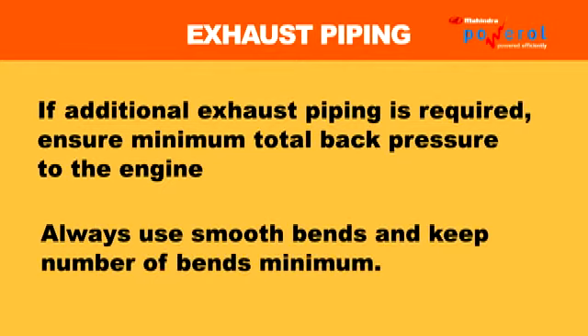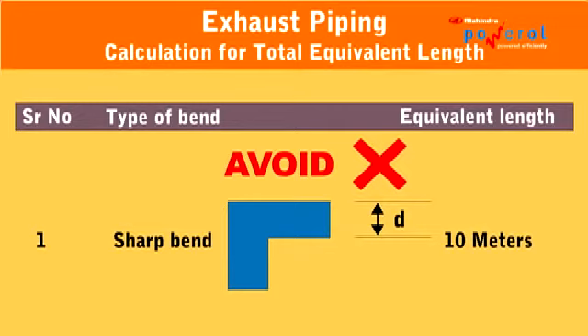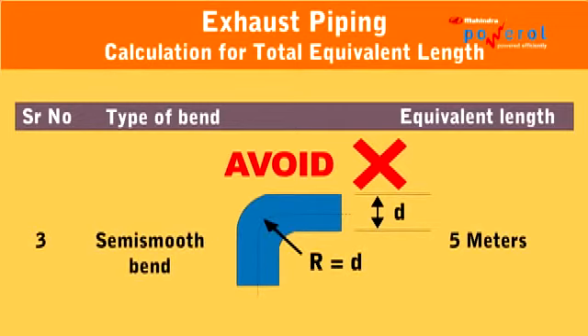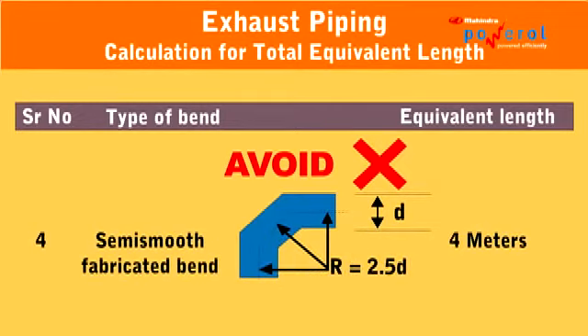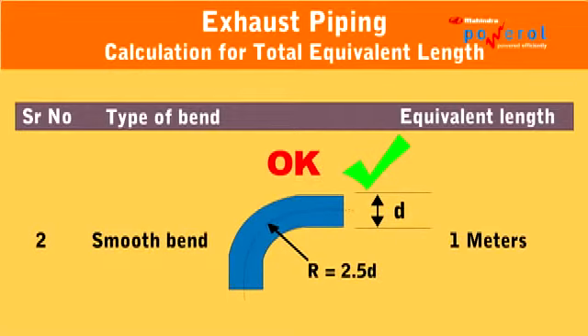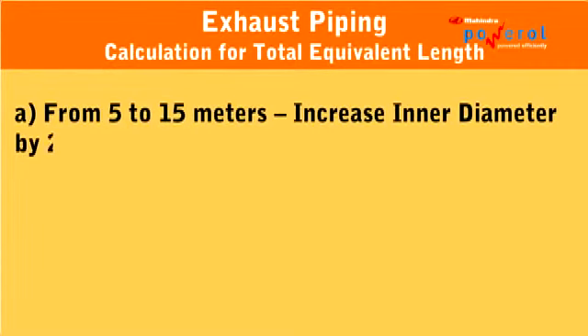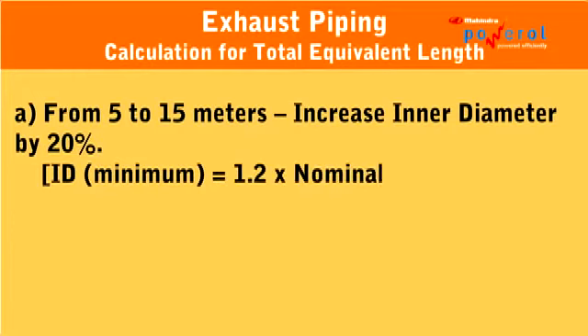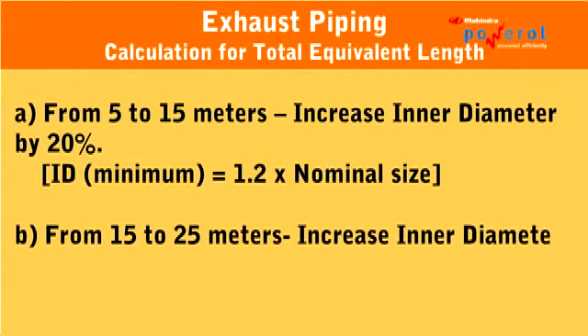Keep the number of bends minimum to ensure minimum back pressure. Excessive back pressure will result in poor engine performance. Always use smooth bends. Have a look at the table of bends. After noting down the number of bends and type of bends involved, calculate the total equivalent length.